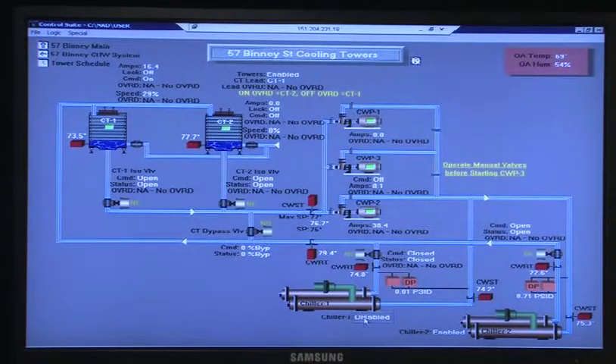This one's saying it's disabled, so this command valve right here is closed. So all the water's coming down through, coming up here, heading down this way, not going through the bypass, because it's zeroed out, so it's not going anywhere. So it's going up to the tower, top, feeding in both towers.